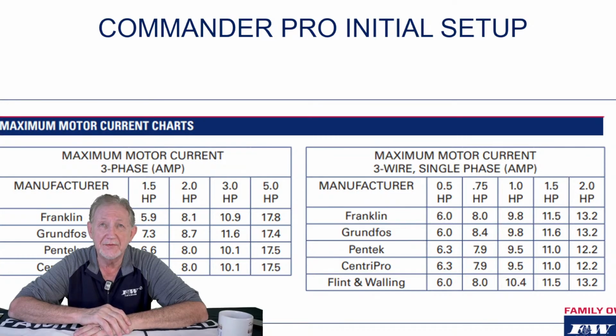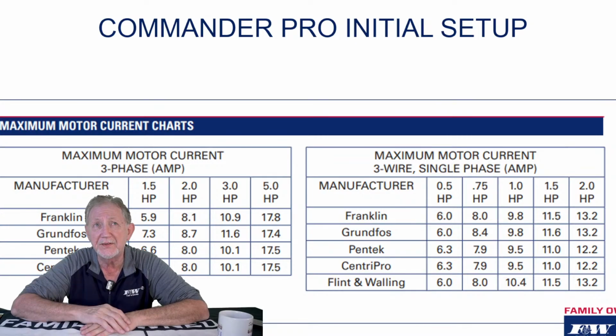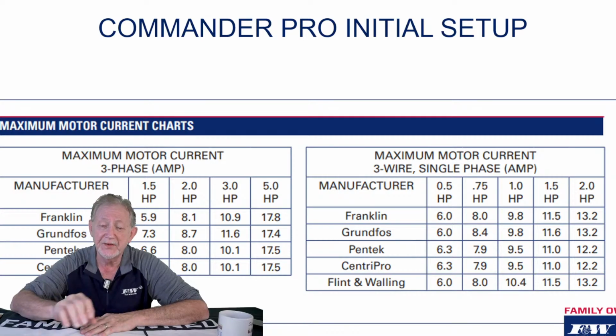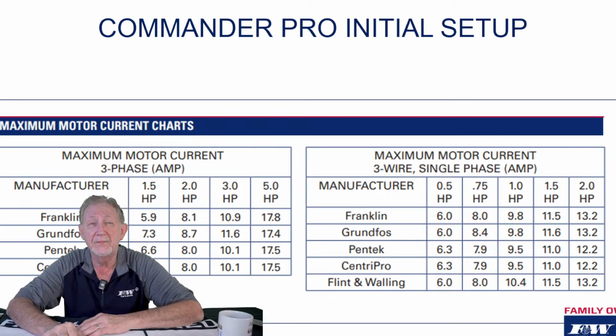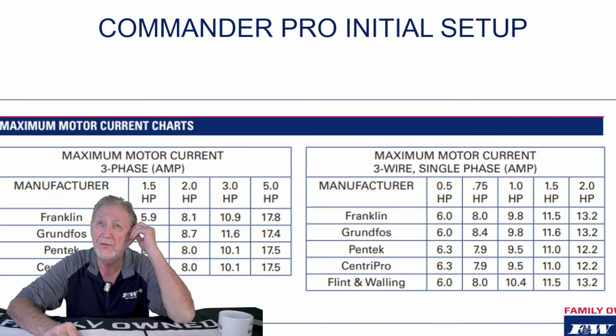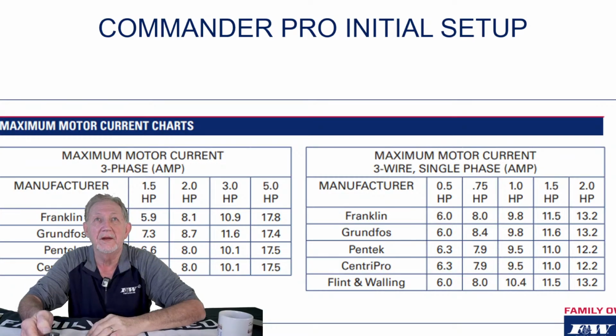Also in that quick start guide is this information, all right? This is max motor amps. Very important to know this because that's how we're going to set the drive up. We're not going to choose a horsepower. We're going to set it up based on max motor amps, because there are different motors out there, and even though the horsepowers may be like horsepowers, the max motor amps could be different for those different motors. And so, as you can see in the quick start guide, we've got the 3-phase listed out, 1.5 through 5, and then the single phase 1/2 through 2. And you've got several manufacturers there, so there's where your max motor amps are going to be located, all right?